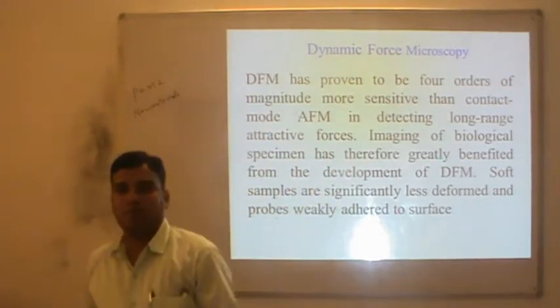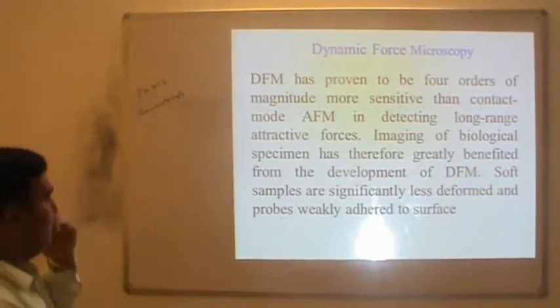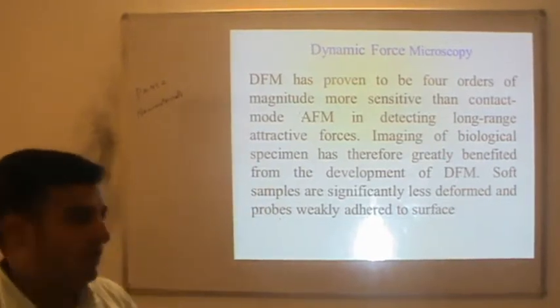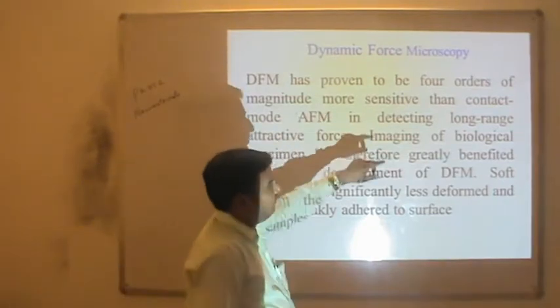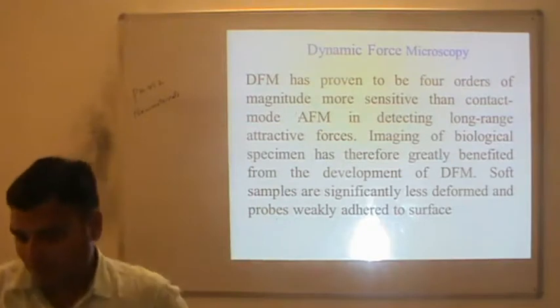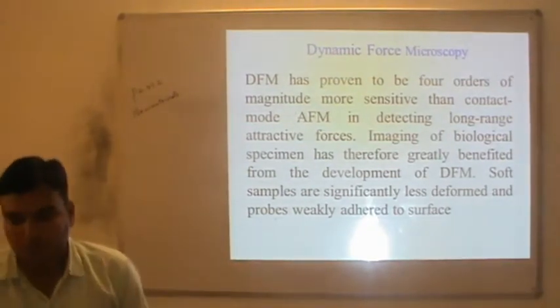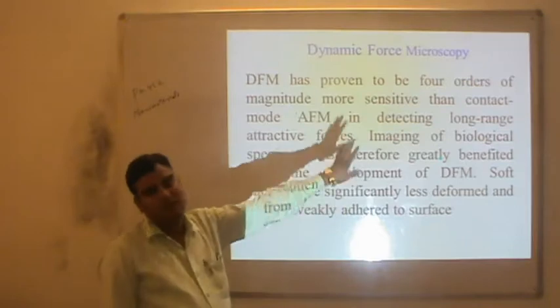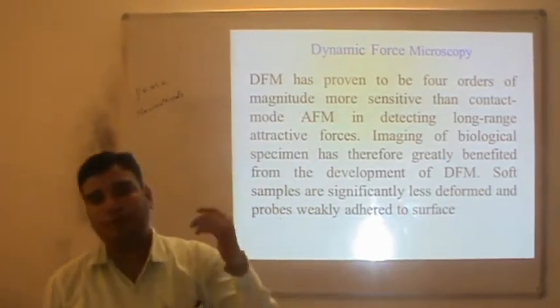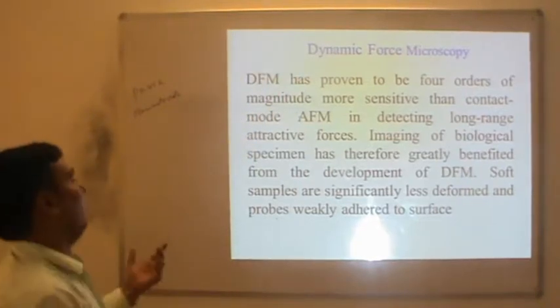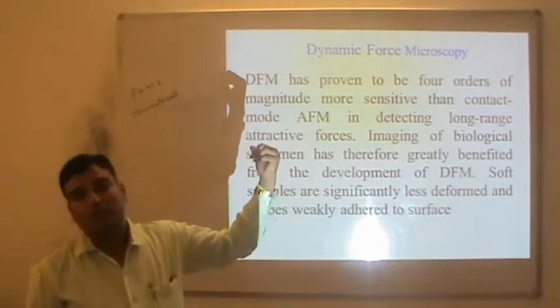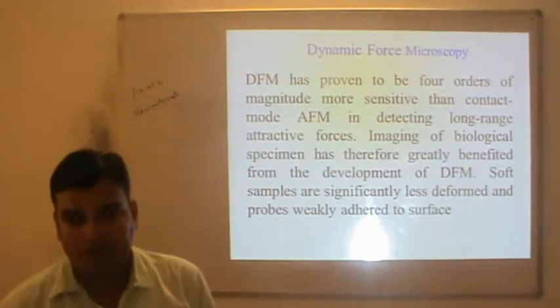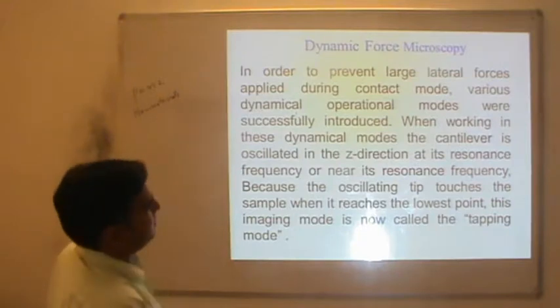The beauty of DFM is that in tapping mode we get more information — approximately four orders of magnitude (around 10,000 times) better than contact mode AFM used earlier. Imaging of biological samples is greatly benefited from DFM. Soft samples are significantly less deformed and weakly adhere to the surface. In dynamic force microscopy, biological or soft samples are never damaged using the tapping mode.